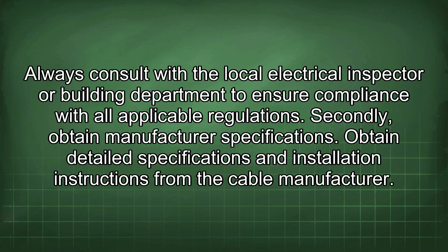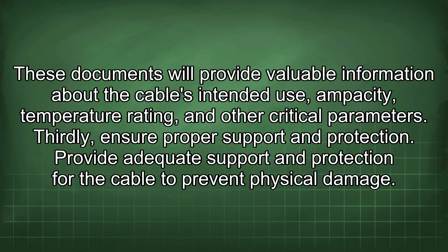Secondly, obtain manufacturer specifications. Obtain detailed specifications and installation instructions from the cable manufacturer. These documents will provide valuable information about the cable's intended use, ampacity, temperature rating, and other critical parameters. Thirdly, ensure proper support and protection. Provide adequate support and protection for the cable to prevent physical damage. This may involve using cable ties, straps, or other approved methods to secure the cable to structural members.